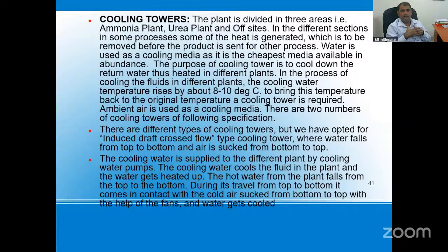Energy transfer takes place, and the water gets heated. This heated water cannot be utilized anymore, but we cannot waste the water. To make this heated water available for use in the plant, the system passes it through the cooling tower, where it gets cooled down to a certain temperature and is available for reuse.